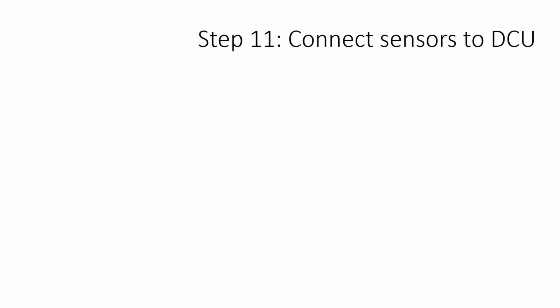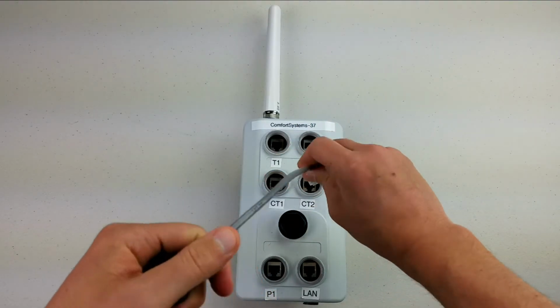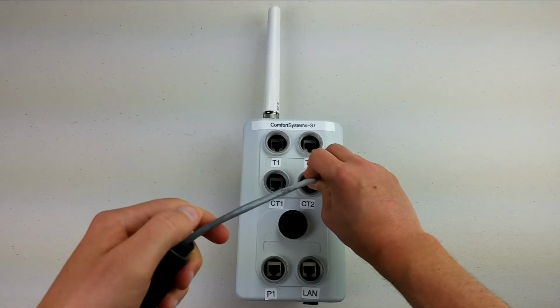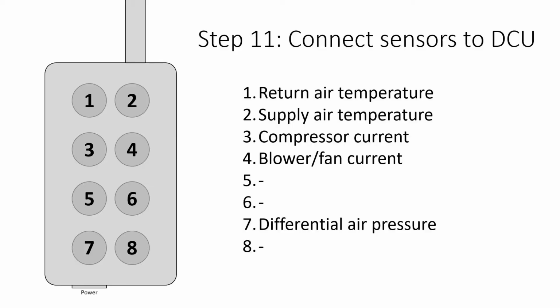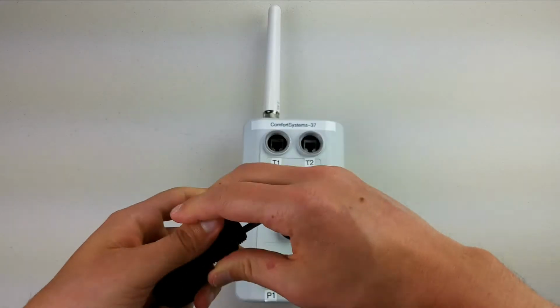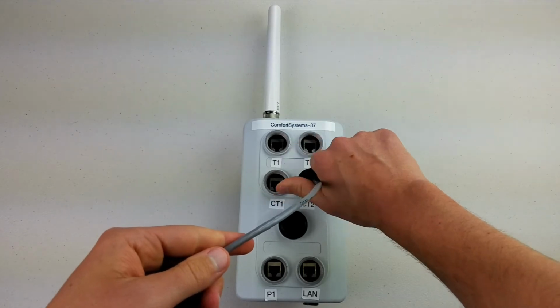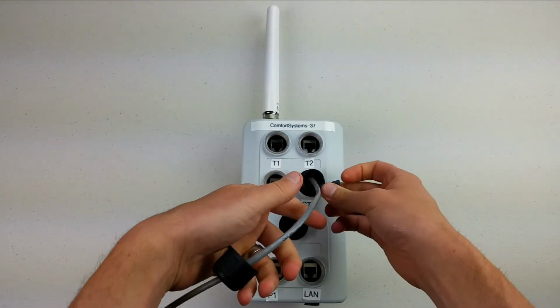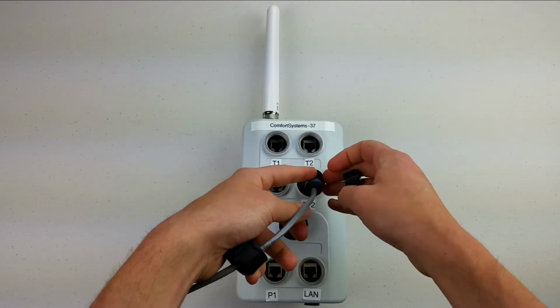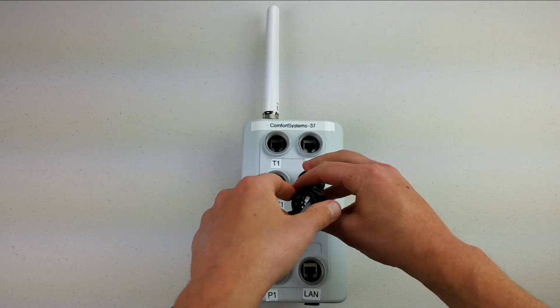Step 11. Install sensor cables on DCU. Plug in the male end of each sensor cable into the corresponding female RJ45 socket. Wait to hear the click and ensure that the cable is properly installed. Refer to this diagram to determine which ports to use for each sensor cable. It is also included in the installation instructions included in the packaging. After sensor cables have been plugged in, screw the cable gland body into the DCU case, add the seal to the wire, and fasten the sealing nut.